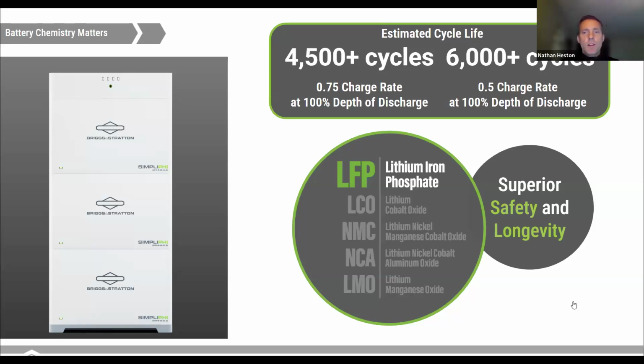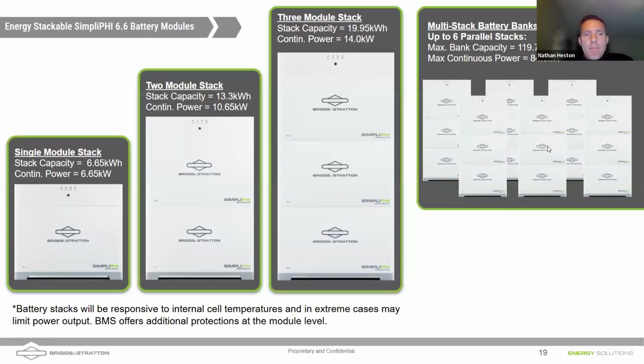It also uses LFP chemistry, which is the only chemistry that you should be using on residential home backup at this time. It's safer, more cycles. There are a lot of advantages to LFP battery chemistry. These batteries can be combined, and I'm going to be talking about how to do some of the settings here in a little bit. We can do stacks, single stack of batteries. You can do double stack of batteries, triple stack of batteries. You can do up to 6 of these stacks for a very large system, 120 kilowatt hour system.